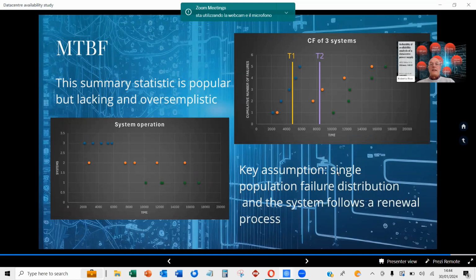Once there is an inability to provide power when requested, that's obviously more critical. If we look at MTBF for, say, three systems - blue, orange, and green - with the blue system operating up to 8,000 and the orange and green up to 18,000, we get an exact MTBF between the three systems. But this MTBF doesn't account for the fact that the systems have been operating for different times, and at one point, looking at the cumulative function, a system terminates and stops being part of the equation.